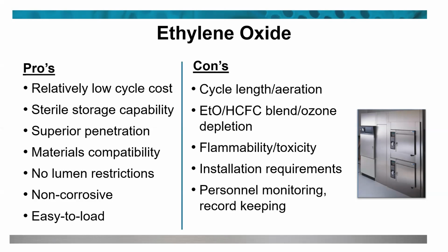It does have disadvantages, however. It's a highly effective sterilant. Times can be lengthy, 1 to 4 hours of exposure, but the real problem becomes the amount of time that it takes to aerate the instruments after they're exposed. And sometimes aeration can take up to 8 hours or longer. It's hazardous: toxicity, flammability in here. So we have to be careful with that.